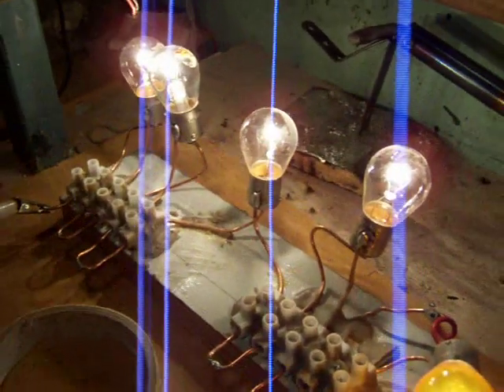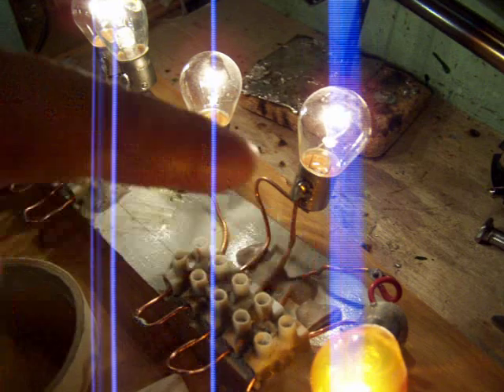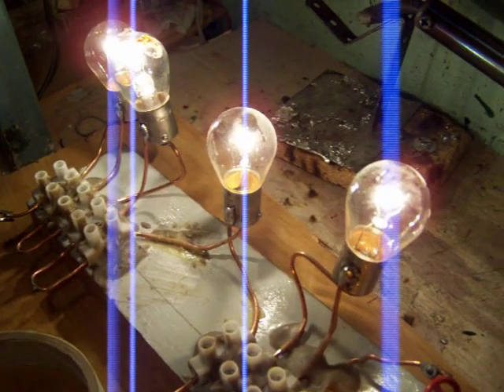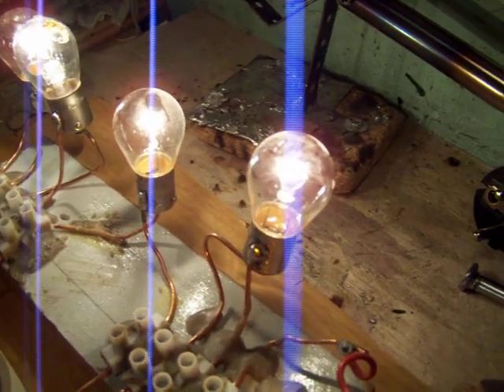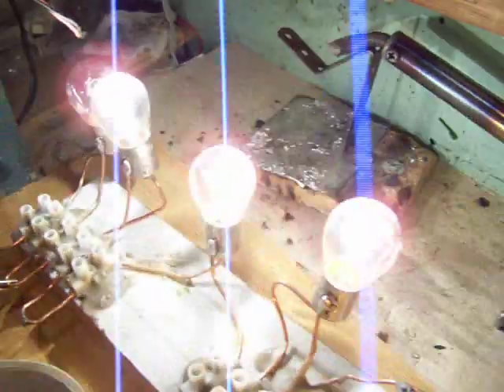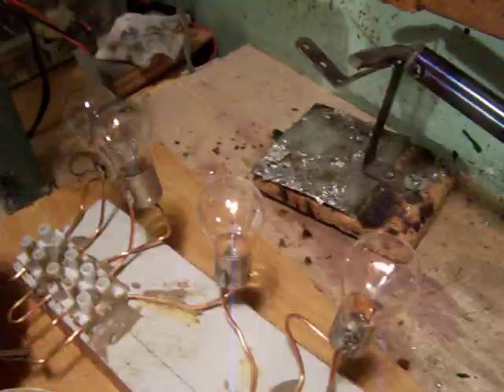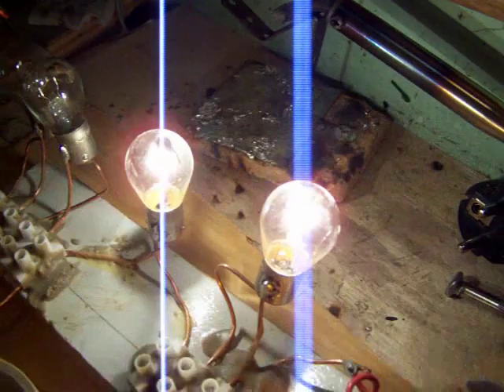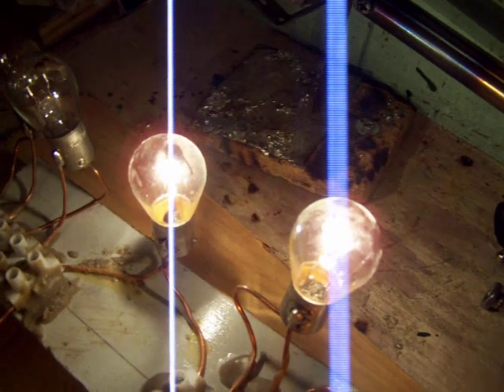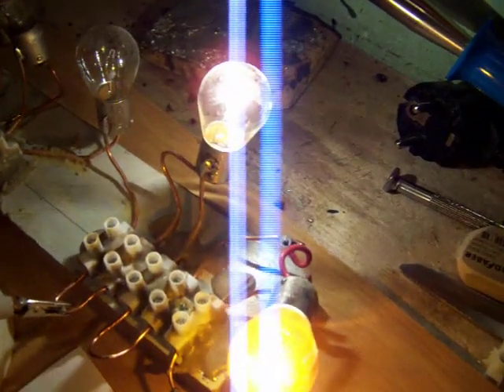When you have a lamp bank, always start with the highest resistance for safety reasons. So all the lamps in series give the highest resistance to test the transformer winding. And when you see that it works, you can shut out one lamp or two lamps, and of course the other lamps light up with much more power now. But it can give you an indication about how much power a separate winding from one transformer can give.